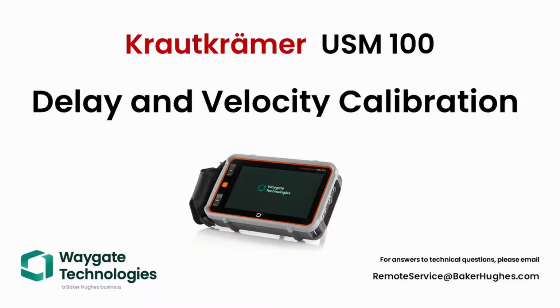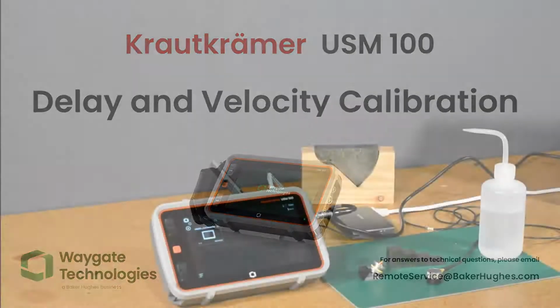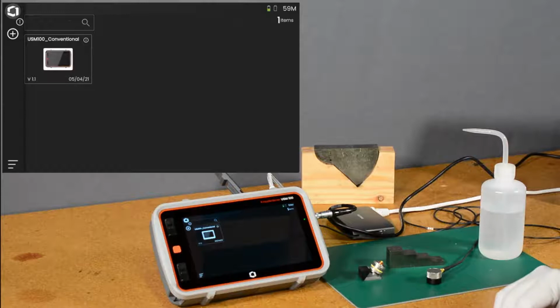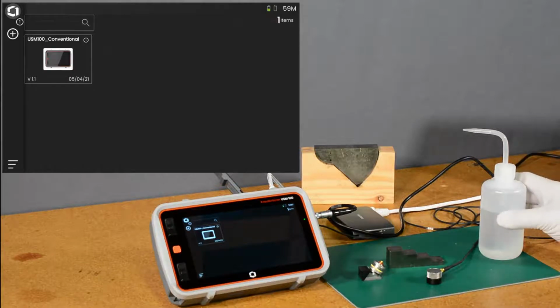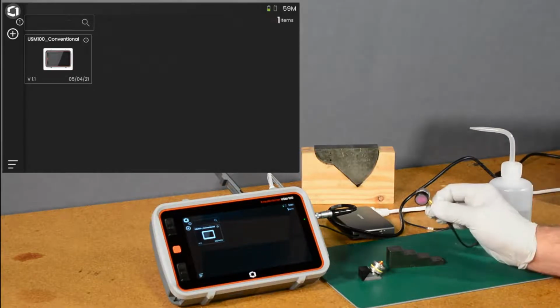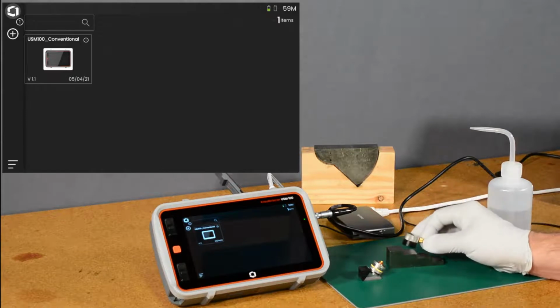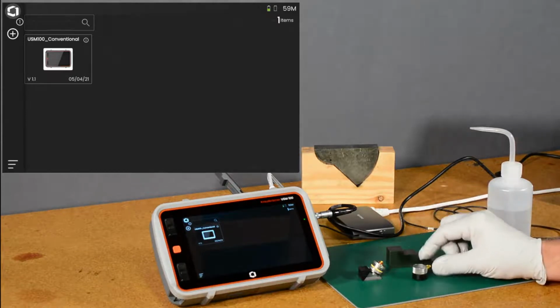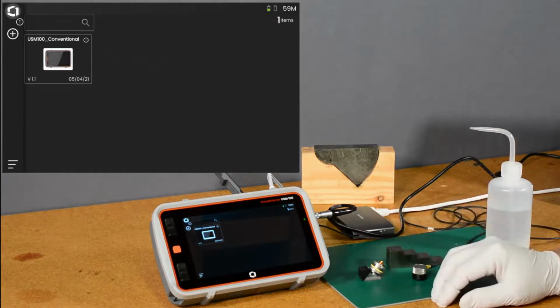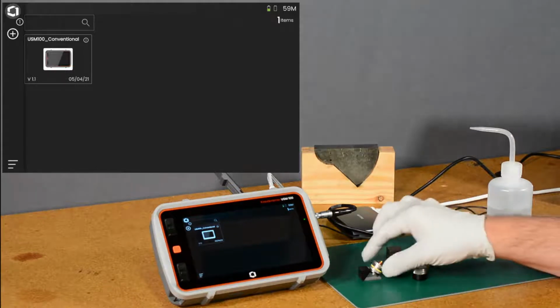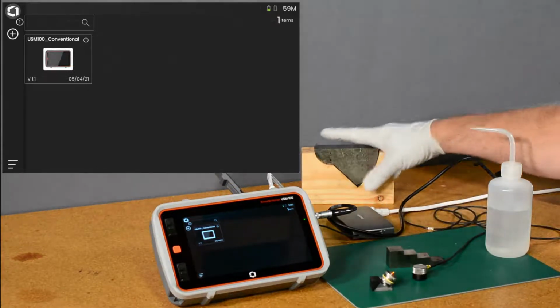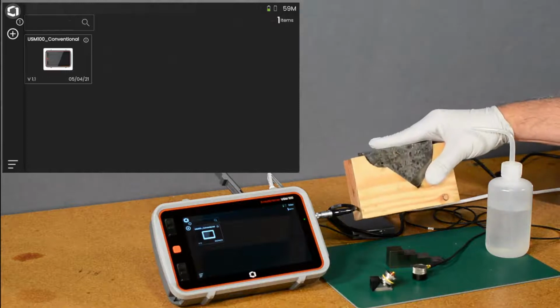flaw detector. Today I'd like to show you a little bit about our 2-point calibration features. We're going to look at two different ways of doing this. In the first, we're going to look at using a straight beam probe on a traditional step block. Show you a quick way to get that dialed in. And then we'll look at an angle beam probe on our DSC calibration block.